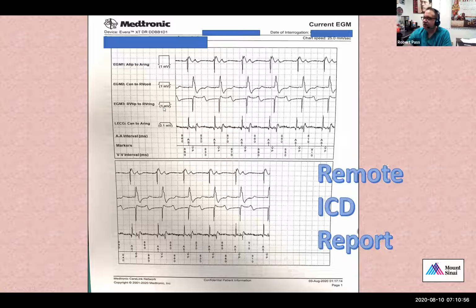And you can see it gives you actually a scale of 1 millivolt. So just eyeballing this, we can see that the RV electrogram is at least, I would say, 12.5 or even 15 millivolts. So that's good, right? We always want the electrogram, particularly in a defibrillator, to be very large. And the reason we want it to be large is because if the patient is in tachycardia, we want it to be able to see what's going on. And so the larger the electrogram, the more likely the device will be to see all arrhythmias at all times.